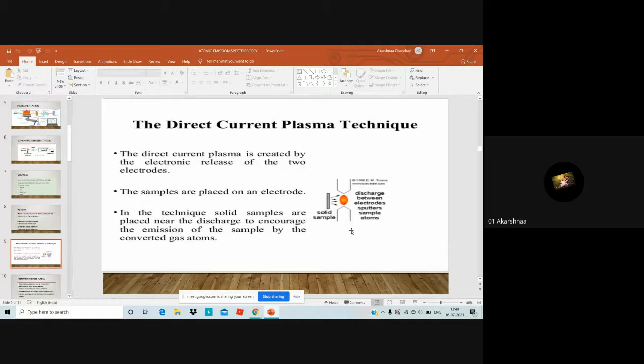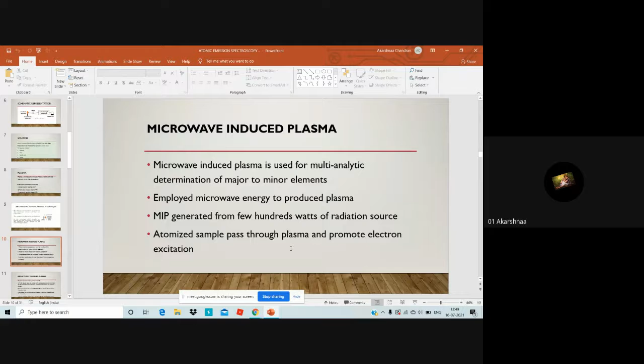Direct current plasma technique. The current plasma is created by electrical discharge between two electrodes. The samples are placed on the electrode. In this technique, the solid samples are placed near the discharge to encourage the emission of the sample by converting it to gas atoms. About microwave induced plasma, it is used for multi-analyte determination of major to minor elements. It employs microwave energy to produce plasma, generated from a few hundred watts of radiation source. Atomized sample passes through the plasma and promotes electron excitation.